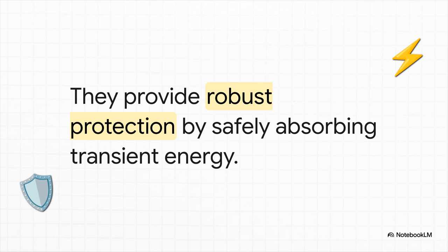They operate on the principle of nonlinear impedance clamping. Under normal steady-state voltage, they basically just act like an insulator. But the moment a high-voltage transient hits, their impedance drops dramatically, allowing them to instantly conduct the surge to ground, safely absorbing that transient energy before it can tear through a transformer winding. It's like a pressure relief valve for the grid.